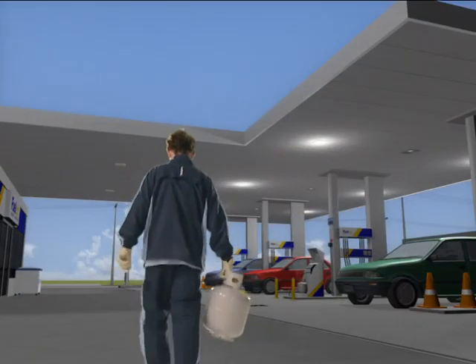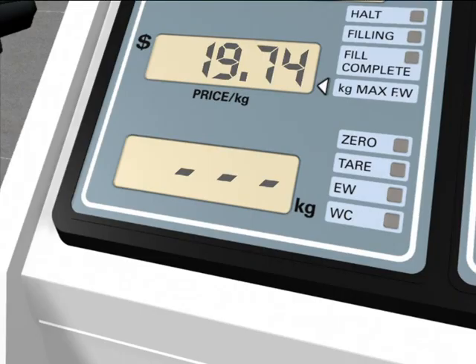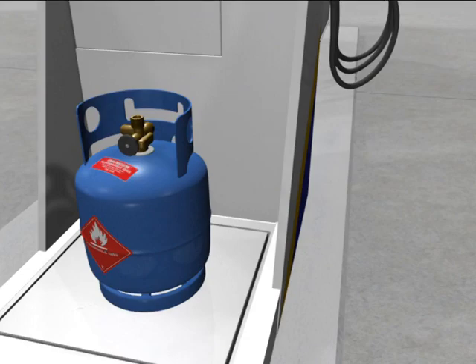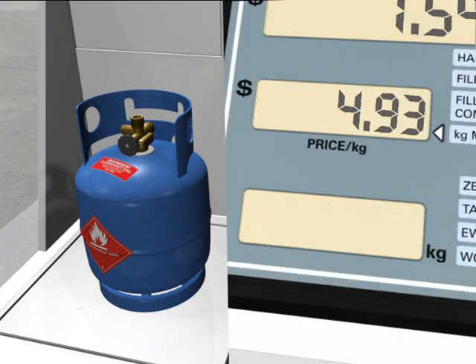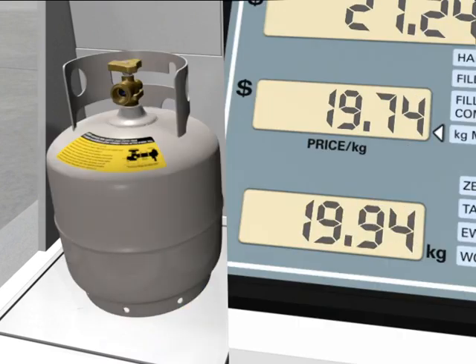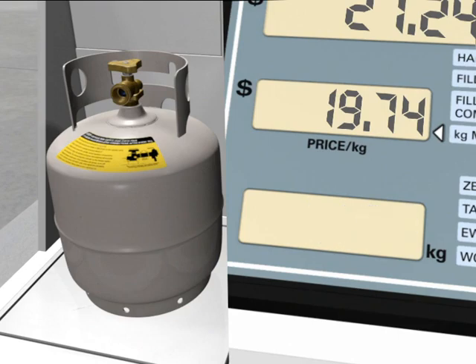If you're emptying an overfilled cylinder, check its weight to see if you're done. Remember the overfill limits: 100 grams for a cylinder under 5 kilograms and 200 grams for cylinders over 5 kilograms.